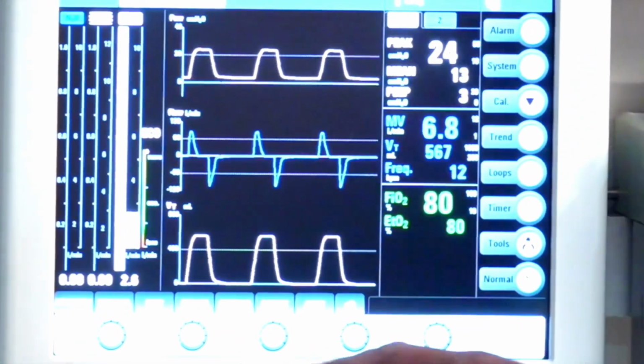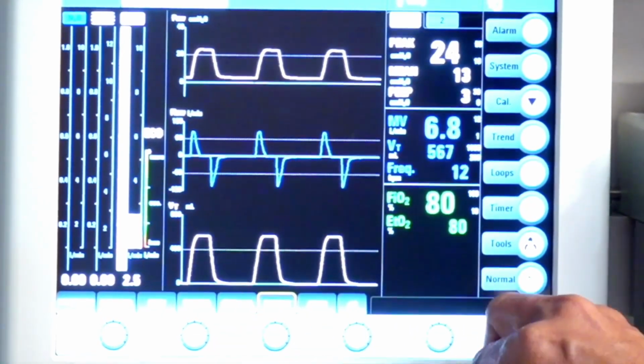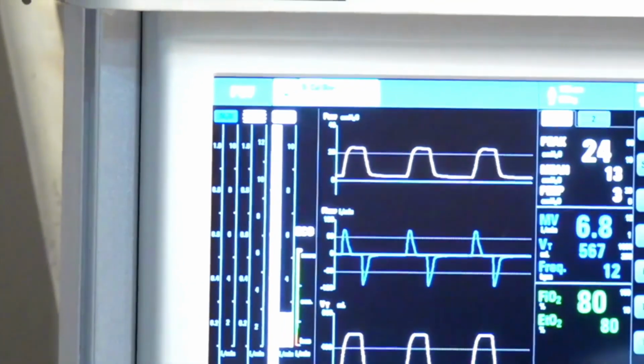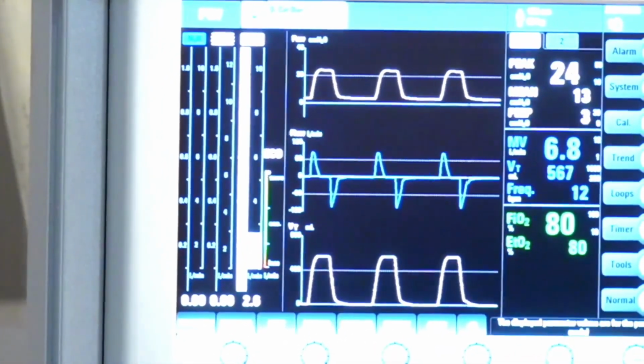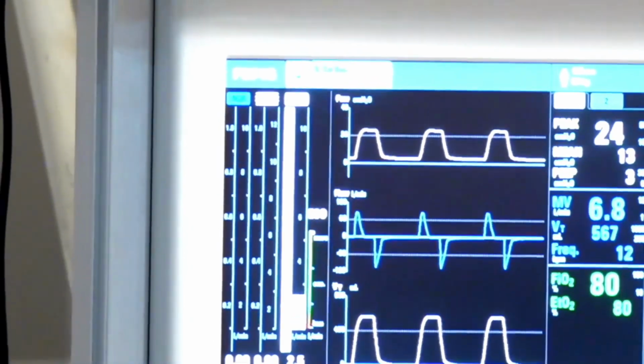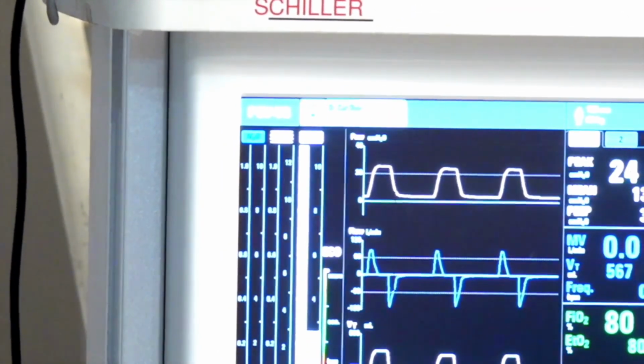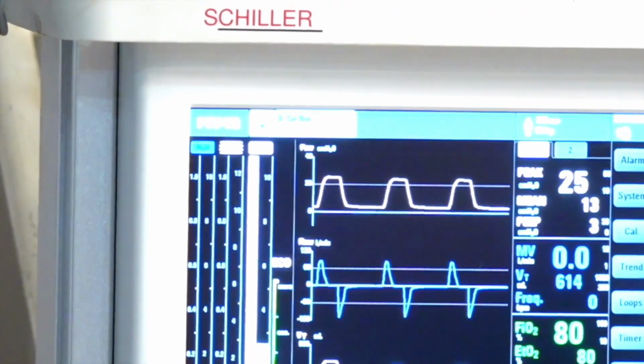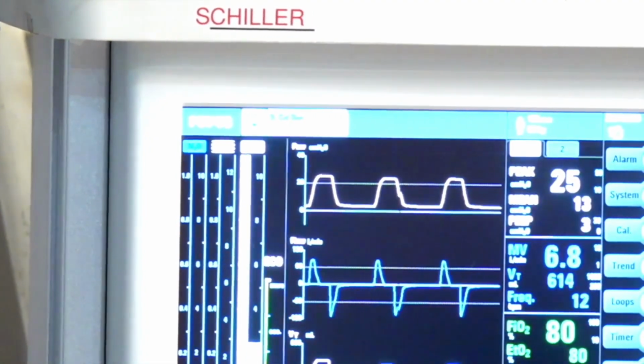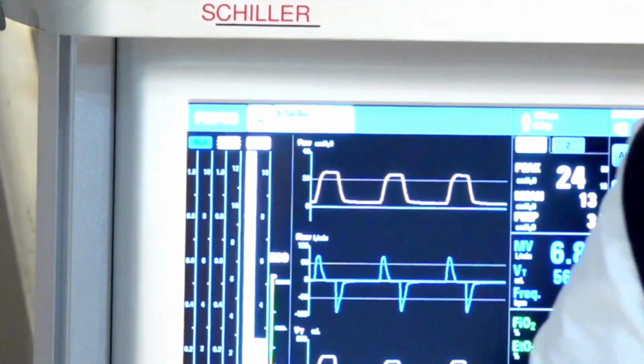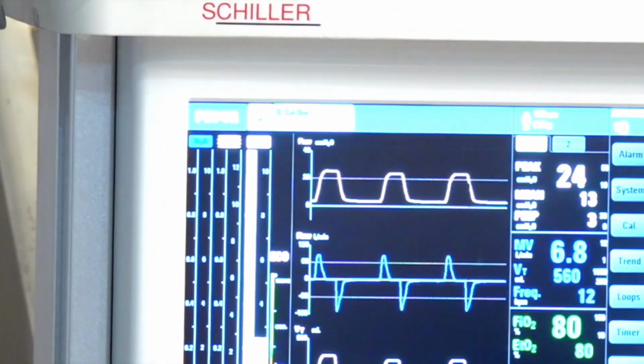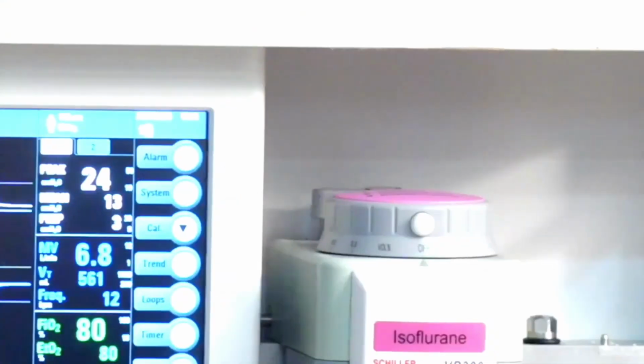So what it will do? We'll change to PCV VG now. When you change to PCV VG, we have set 560. Okay. So when I change over, it will take probably a control mode first. Once it is giving control mode and identifying the compliance, it will start getting it there. Now, since this is not an actual lung, it will gradually improve the tidal volume with changing flow, and it will get you to your targeted tidal volume with the optimum flow and the pressure.